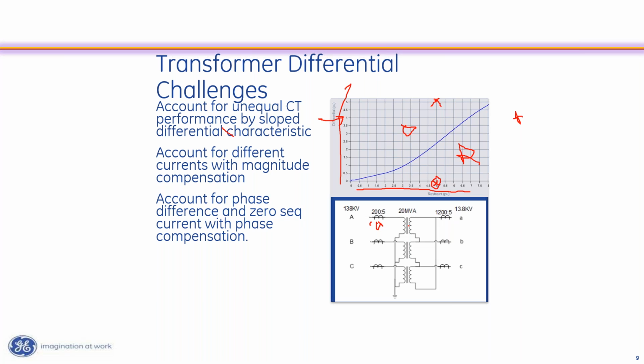There's another thing that I've got to account for in the fact that this current here, it's at 0 degrees. This one over here, where my CT is at, it's not at 180 degrees. It's probably at minus 30 degrees, right? So the X winding is lagging the H winding by 30 degrees. So instead of the current being presented to the relay being at 180, it's probably at minus 210 because of that 30-degree phase shift. And because of that, I've got to take care of that. And what I've got to take care of is phase compensation. I've got to take care of the fact that the angles on either side of the transformer are different.